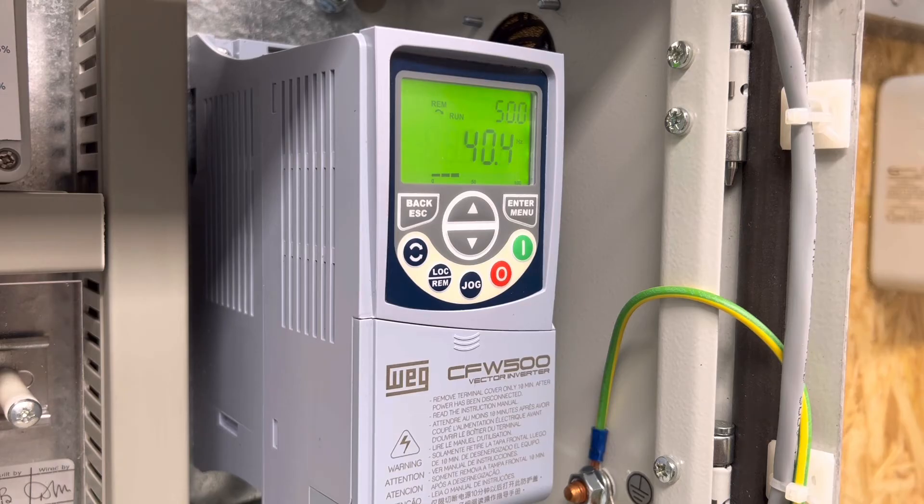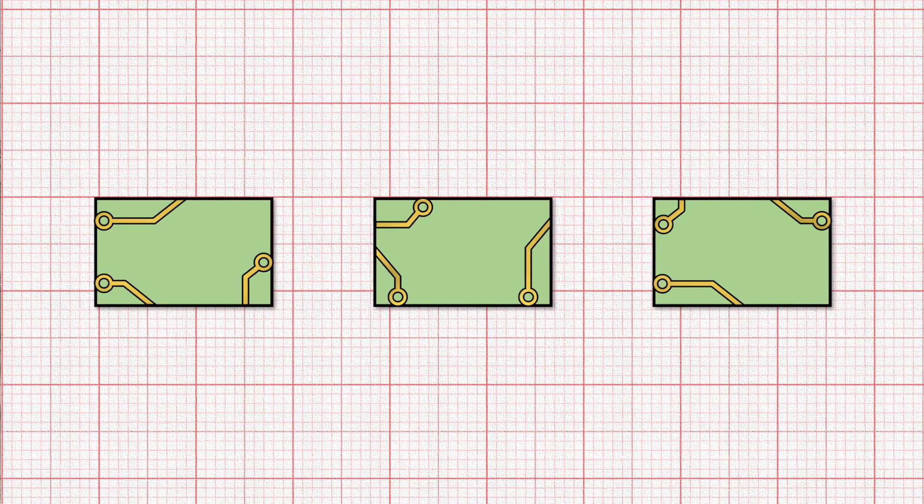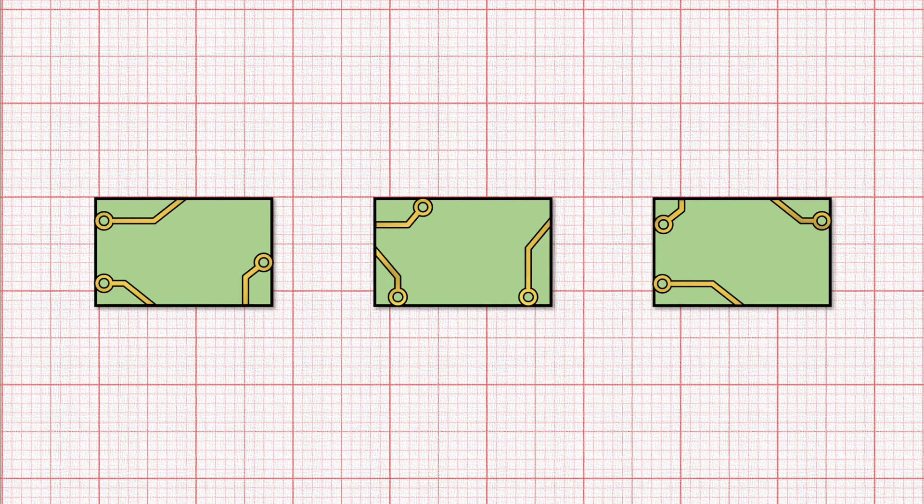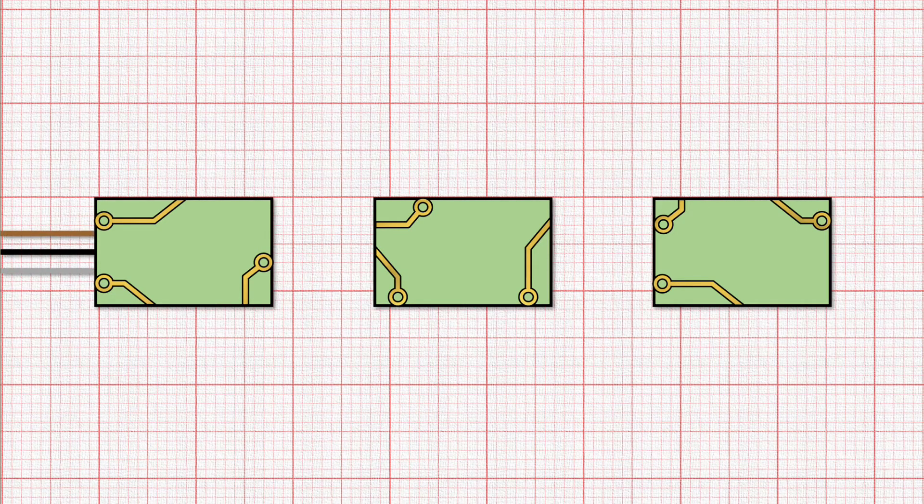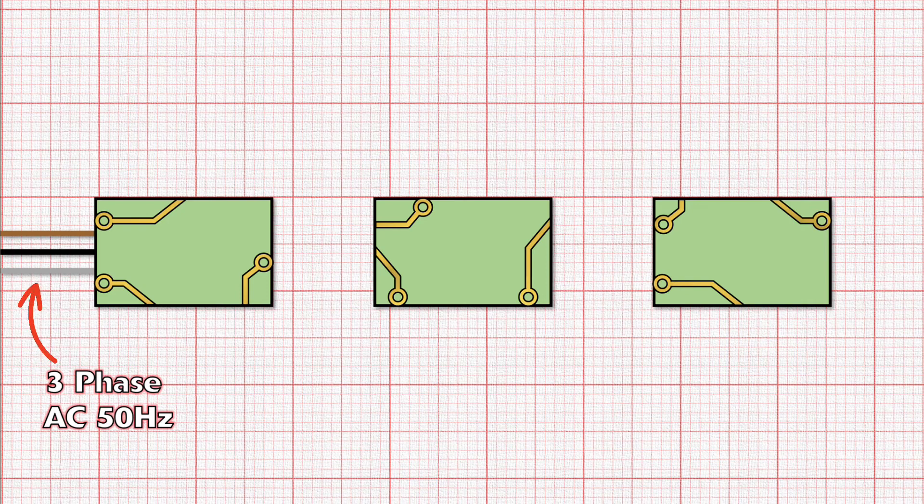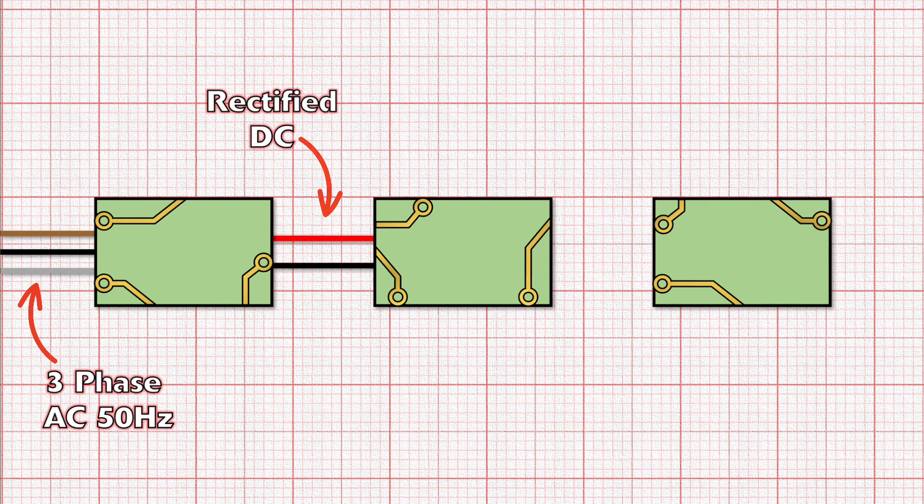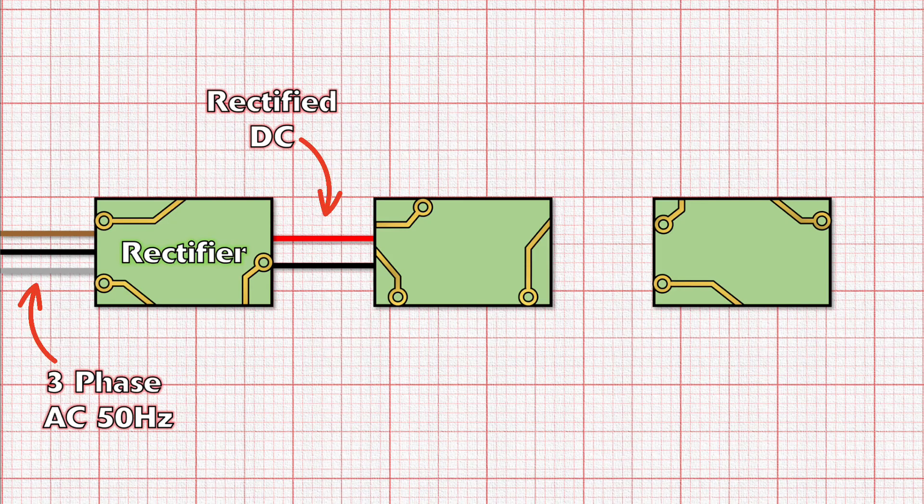We do that by means of a variable frequency drive or VFD. Now these work in what seems like quite a counterintuitive way, because the first thing that a variable frequency drive does is to take the three-phase AC power supply and convert it to DC using a device called a rectifier. The reason why it does this will become clear as we get further into the process of how a VFD works.